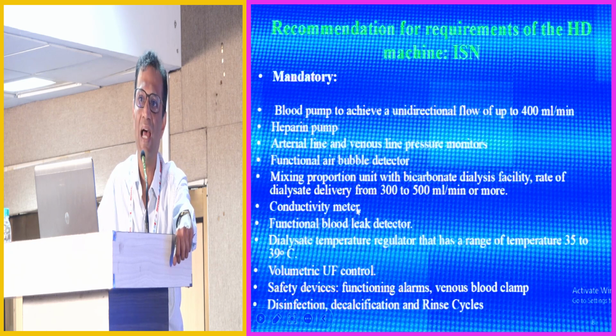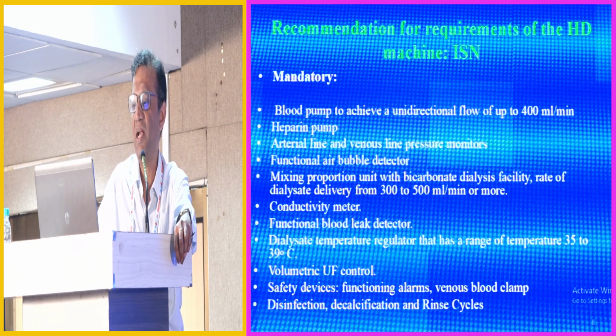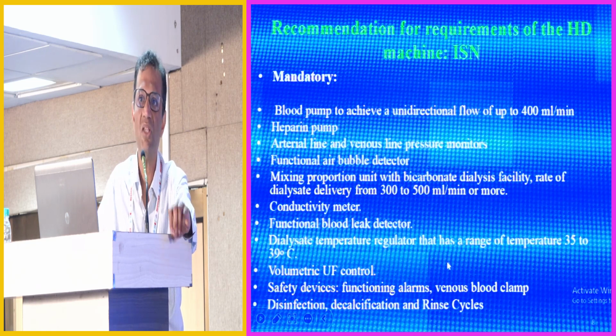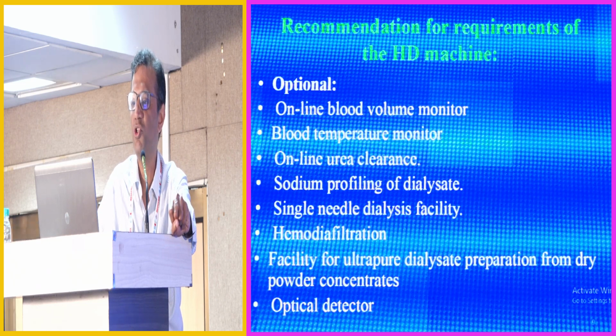It must deliver dialysate of the right composition, that means chemical composition and temperature, at 300 to 500 ml per minute or more. It must prevent blood leak in the case of a dialyzer rupture. It should be detected, and it should produce an accurate ultrafiltration. So how does the machine do all these things?